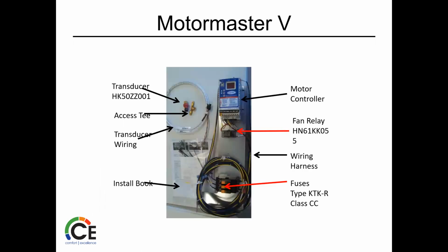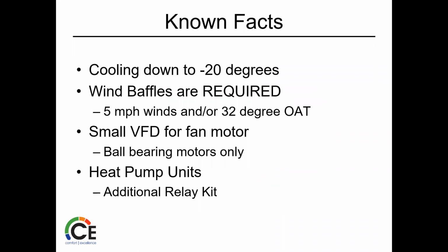So probably the most popular one, I think this one is the one most people like to use. It has a transducer in it. Again, an access T, again, some wiring. It does come with instructions, not just a knee pad, right? They're there for a purpose. Motor controller, fan relay, some wiring harnesses, some fuses. Controls down to -20, so now we're back to -20. Wind baffles are required.